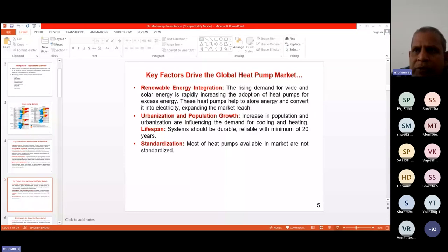The lack of working fluids, because presently we are using working fluids like R134A, R410A, R32, and these are the refrigerants which are commonly used in heat pumps. These fluids are to be completely phased out according to the Paris Protocol 2016. According to this, refrigerants with a global warming potential less than 150 are recommended for usage. So none of the existing fluids are going to be sustained in future.